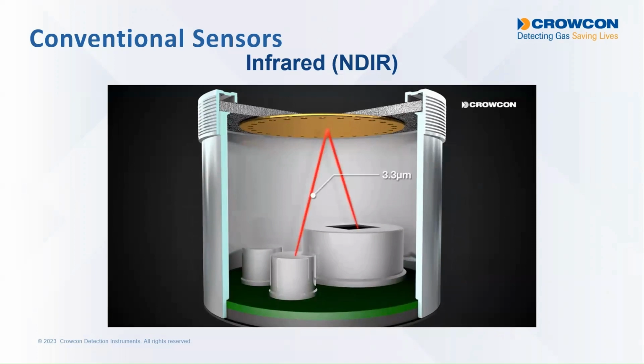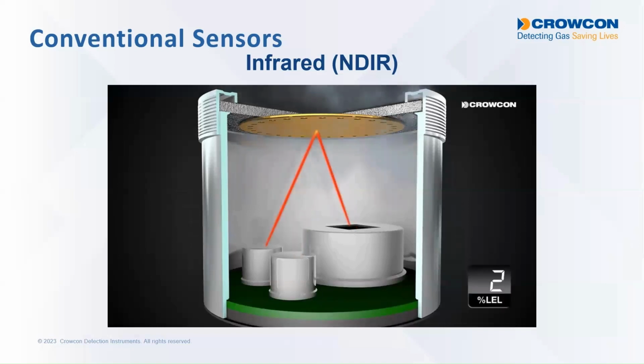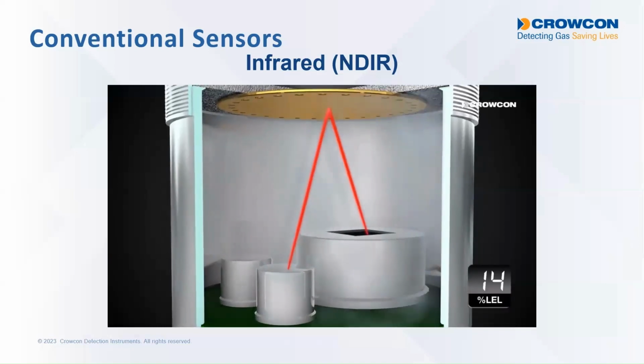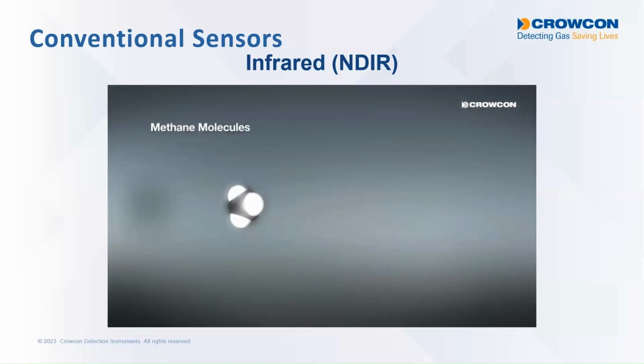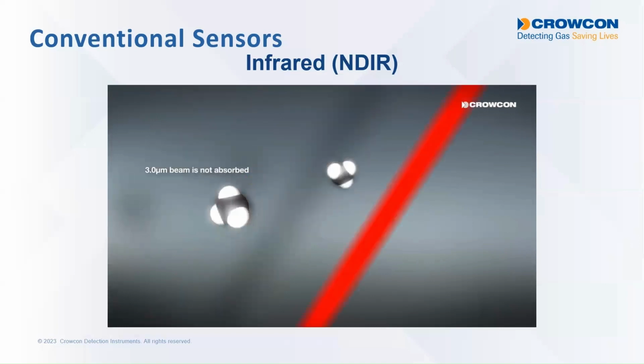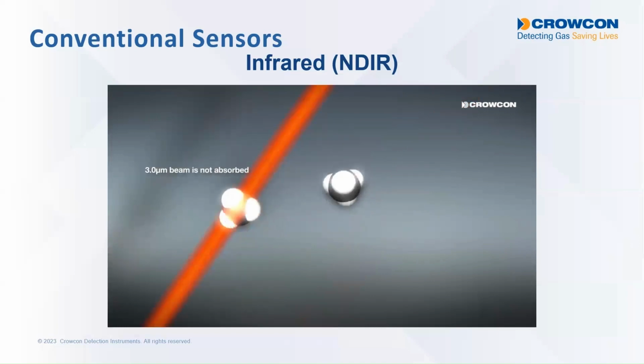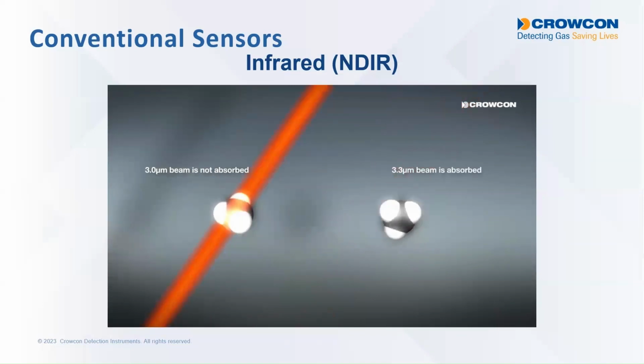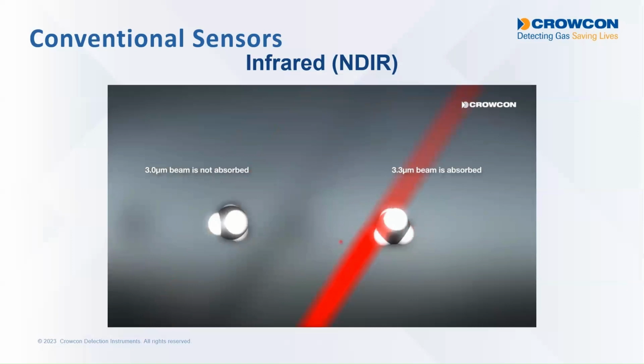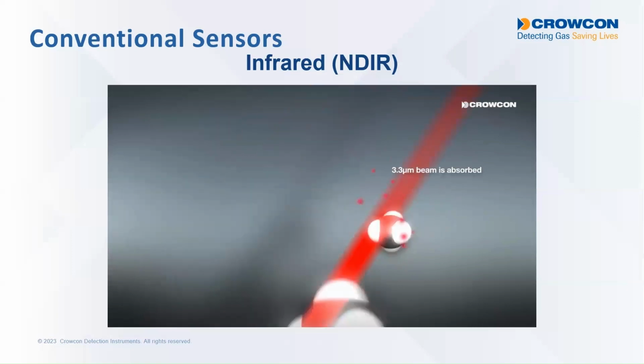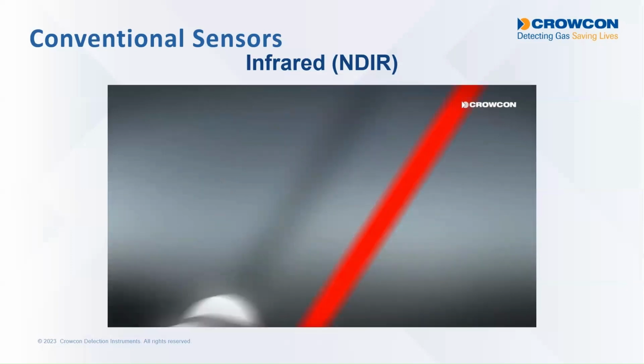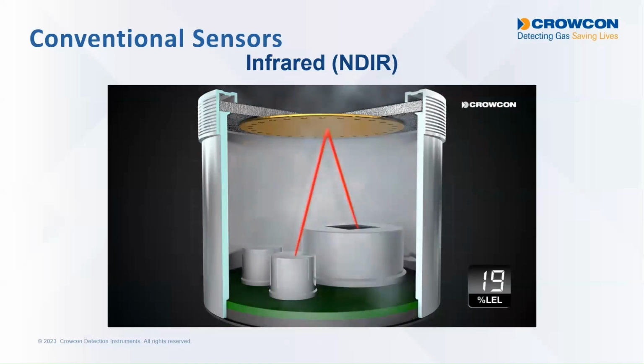So the system is constantly monitoring the two different wavelengths and comparing the output signal of the sensor at the two different wavelengths. So you can see the infrared energy is reflected on a mirror. And as gas enters the sensor, the 3.3 micron energy will be absorbed. So the sensor measures the difference in output from the two sensors, and it can determine gas presence as opposed to energy reduction due to contamination, and give us a % LEL gas reading.